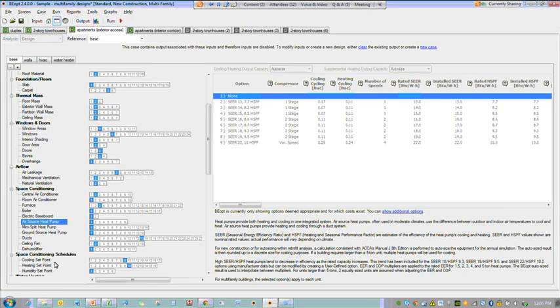And it essentially means that you can have a small oversizing factor if your heating load is larger than your cooling load. Depending on your climate, how dry of a climate it is, how mild of a winter you have, and depending on whether you have single speed, 2-speed, or variable speed equipment, you can oversize the equipment over the design cooling load between 15 and 30% so you have a higher heating capacity so that you're relying on electric resistance heat less.